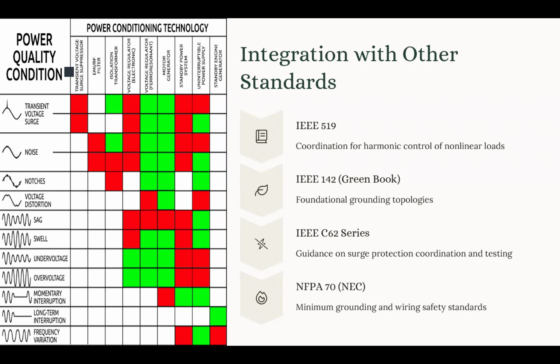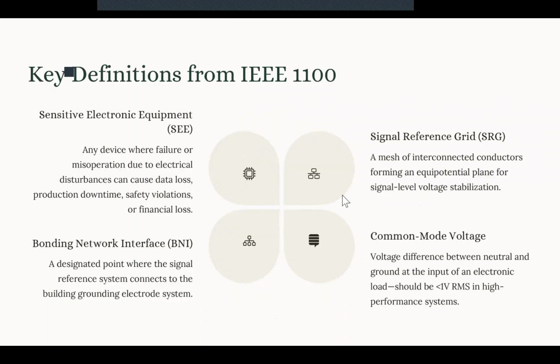We also have the standard NFPA 70, or we could call it the National Electrical Code, NEC, which basically sets the minimum electrical safety standards for wiring and grounding in the electrical system. It makes sure that fault current and personnel safety are addressed, and the NEC defines the criteria for those aspects. And basically, IEEE 1100 extends these to ensure we also have functional reliability. Now, there are some key definitions that we need to mention, and they come from IEEE 1100.